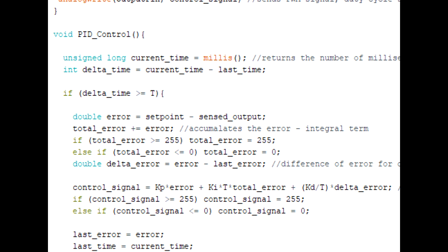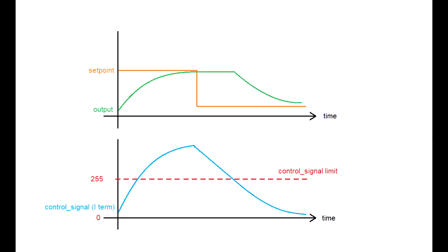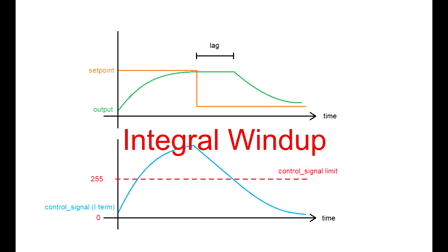We'll also want to do this for our accumulated total error. Because if our total error accumulates past 255, and then let's say there's a drop in the setpoint, it will take a couple iterations for the total error to dissipate back to the 0 to 255 range, and that can cause a time delay on the output. This is known as integral windup.